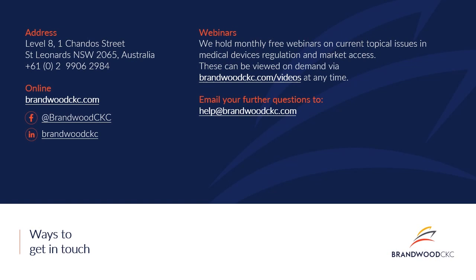Question number 3, do you have any advice on how companies should record and store data/results when conducting clinical trials for their medical device registration? I guess with all clinical trials, we highly recommend that you follow good clinical practice. There are guidance and standards out there which are really helpful. One of them is the ISO 14155 standard. This provides information on recording of the data, the electronic data systems, record retention. They're really useful and really vital for providing information on how to store that data to be then used in your clinical evidence report.